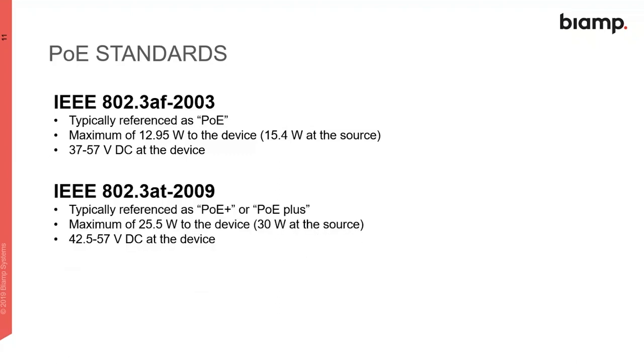In 2009, that wasn't enough, so we came out with a new standard that delivers more power - that's where PoE Plus comes from. We introduced 802.3at, which includes everything from 802.3af but adds additional power to get you up to 25.5 watts at the device. The voltage range is a little tighter, but the nominal voltage is still 48 volts.